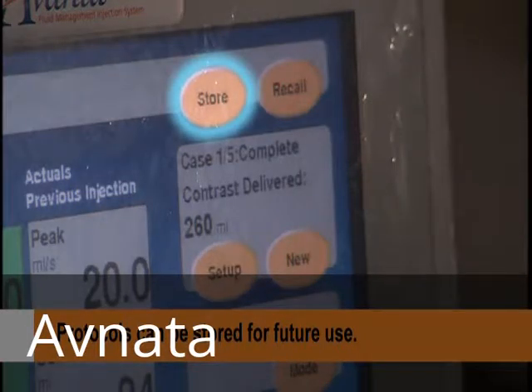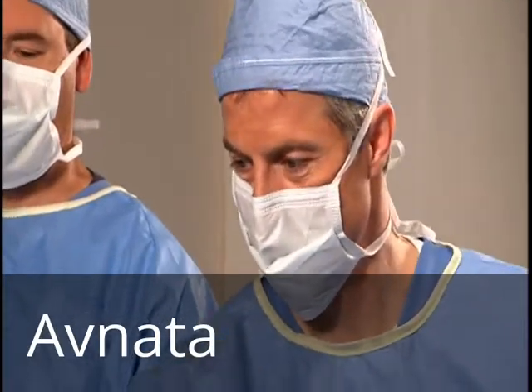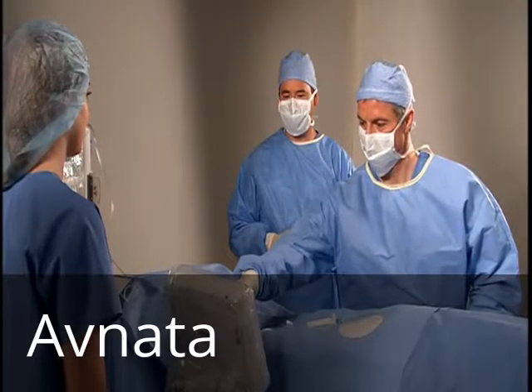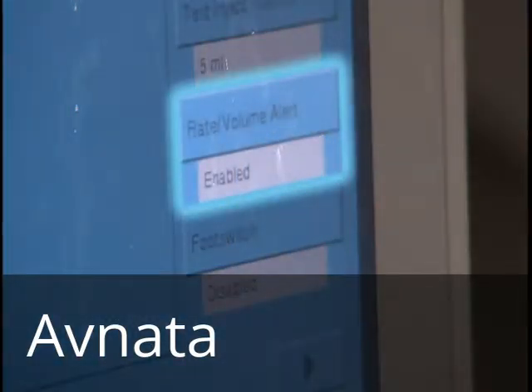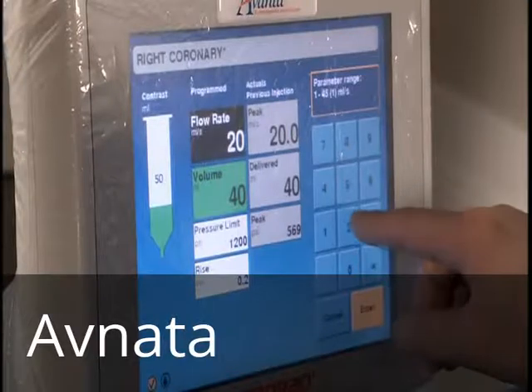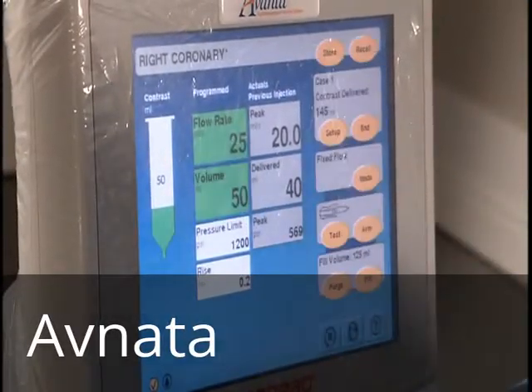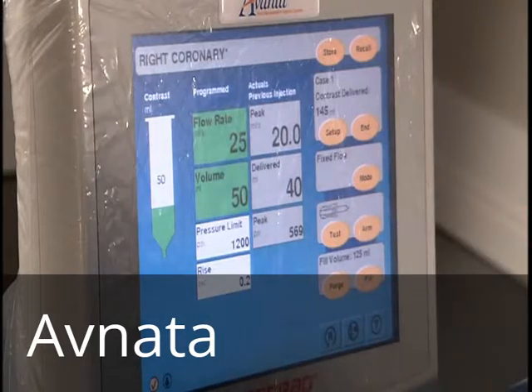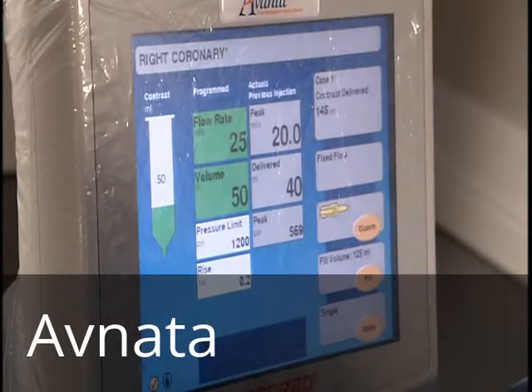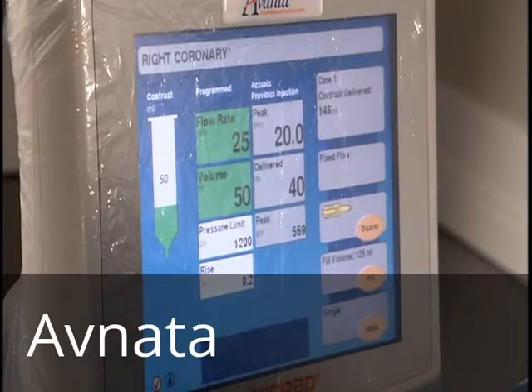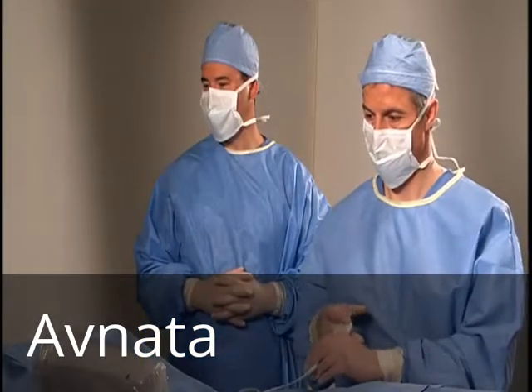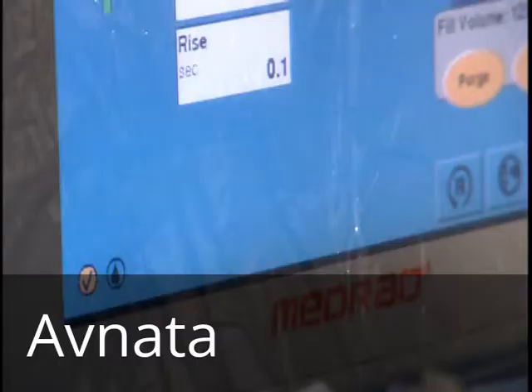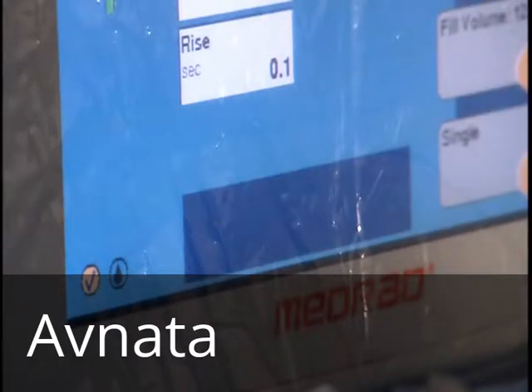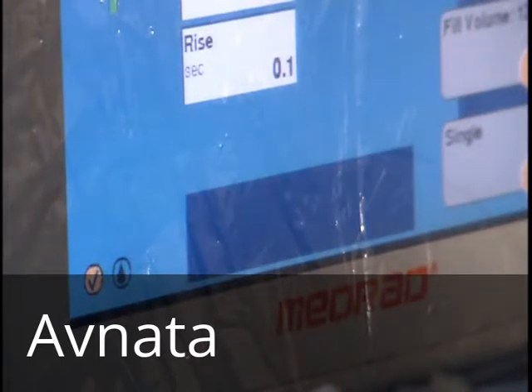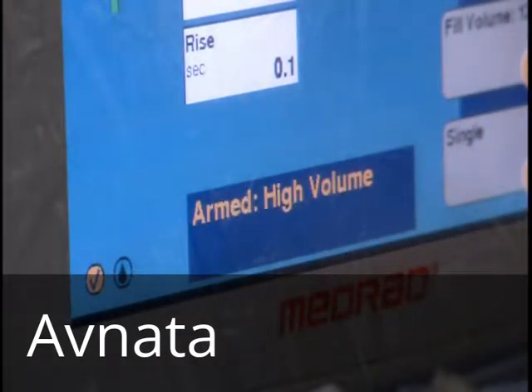An injection protocol can be stored at any time in the system memory for future use. For additional safety, the system can be configured to issue an alert when armed for high flow rate and/or high volume injection via the configuration screen. A high flow rate occurs when the flow rate is greater than 10 milliliters per second in fixed flow mode only. The system beeps 5 times and the message Armed High Rate appears at the bottom of the screen. A high volume alert occurs when the volume is 20 milliliters or greater in either flow mode. The system beeps 5 times and the message Armed High Volume appears at the bottom of the screen.